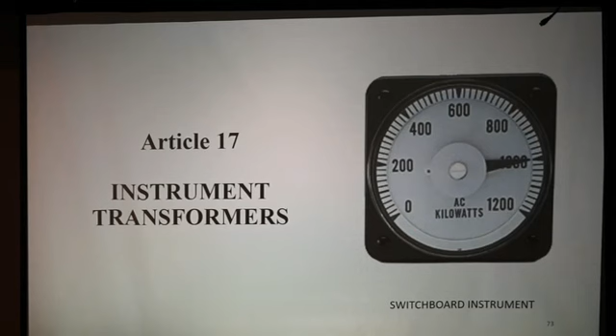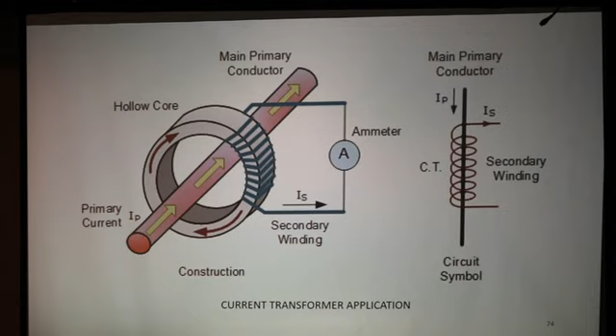In this case, you can't hook your amp meter to a 5,000 amp cable, but if you put a current core transformer around it with a certain ratio of turns - say 10 turns - then if there's 10 amps flowing in the primary wire, there will only be 1 amp flowing in the meter.